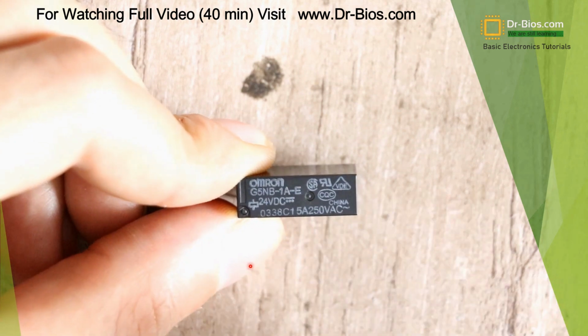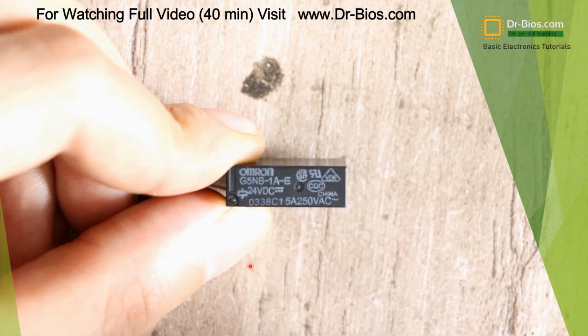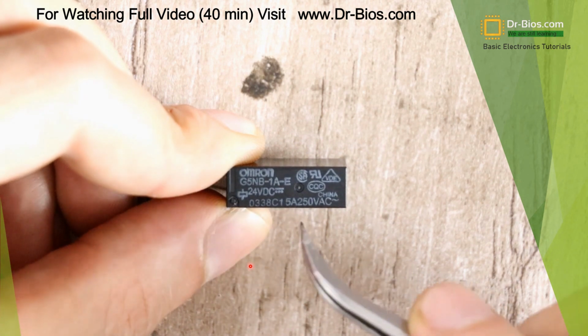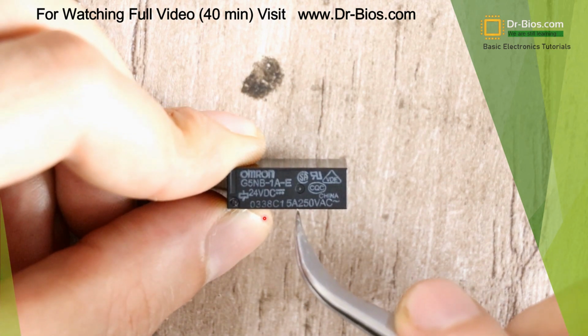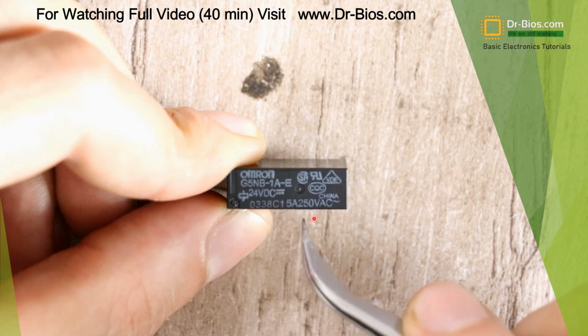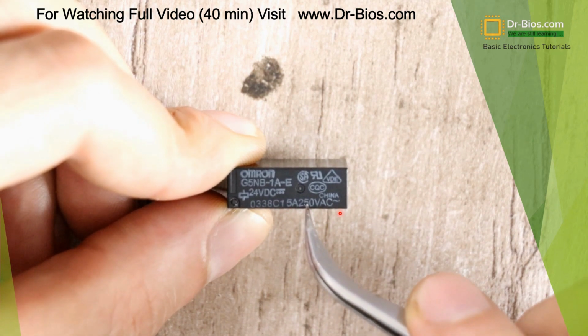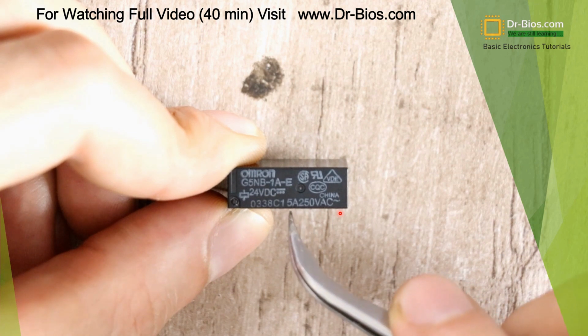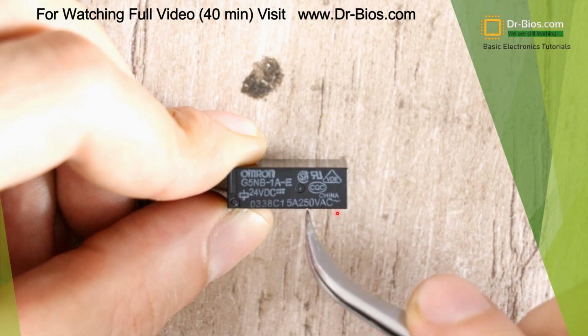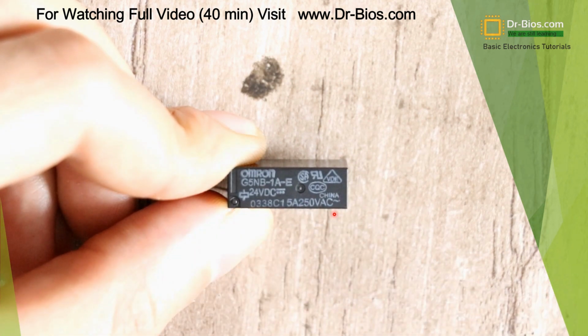Another thing that is written on relay is voltage and current tolerance of secondary side. Secondary side of this specific relay can tolerate 5 ampere and 250 volt AC, and they shouldn't go higher than these values.